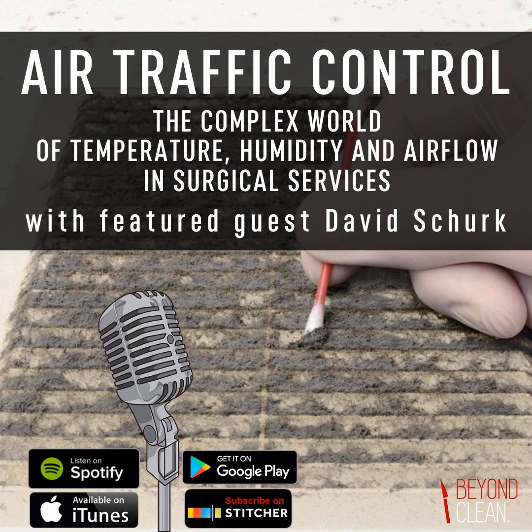Beyond that, particularly in sterile processing, what I see are some of the same issues that are being experienced in operating rooms. Like ORs, they require a program for management and measurement of proper temperature and relative humidity, with regards to the FGI guidelines. But in sterile processing environments, they only list maximum temperatures and relative humidity requirements. And cool and dry requirements may actually be preferred above and beyond what's listed in the standards, because the people working in those sterile processing environments are typically heavily garbed and they're working hard. So they have issues with trying to maintain comfort. They sweat underneath their gowning. The environment needs to be dry enough to be able to absorb the perspiration off their skin through their gowning into the environment. And many times the sterile processing HVAC systems are not designed to be able to obtain or maintain those lower relative humidity set points, very similar to the same issues we see in operating rooms.